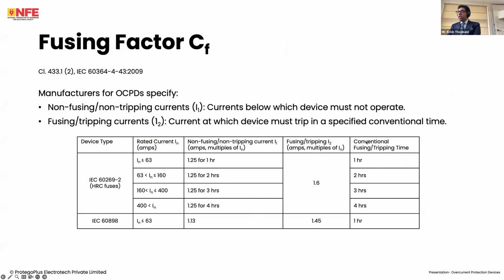Now, the fusing factor, which is what I was talking about earlier. See, like I said, if a 10 amp device is there, once the current exceeds 10 amps, you're not going to actually have the device trip immediately. Or rather, if it's 11 amps, it's not going to trip at all in most cases. So the most common devices we generally use are MCBs, MCCBs, and HRC fuses. So for an MCCB, this depends entirely on the setting we put. So that's not included in this table, obviously.